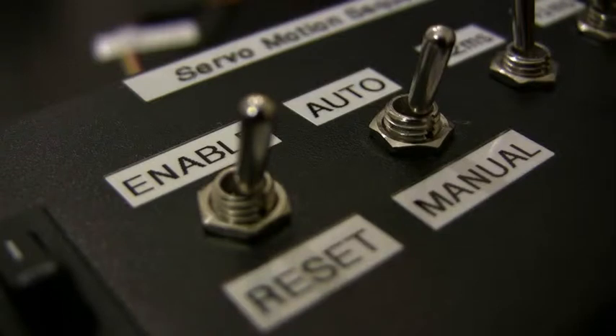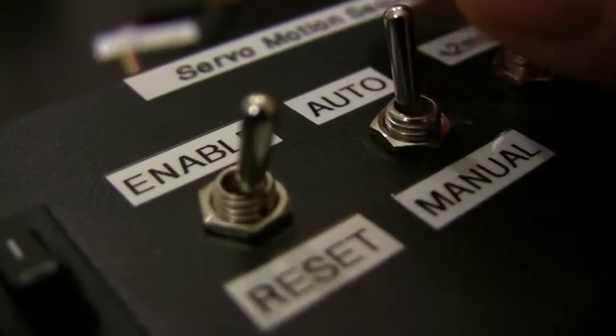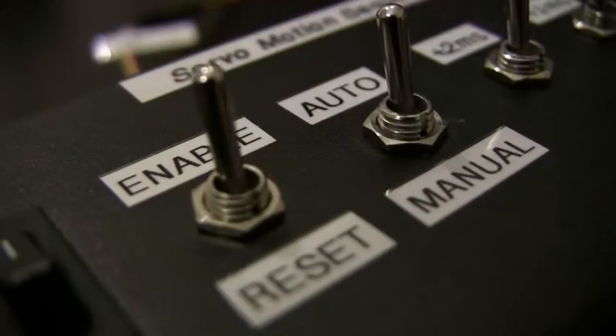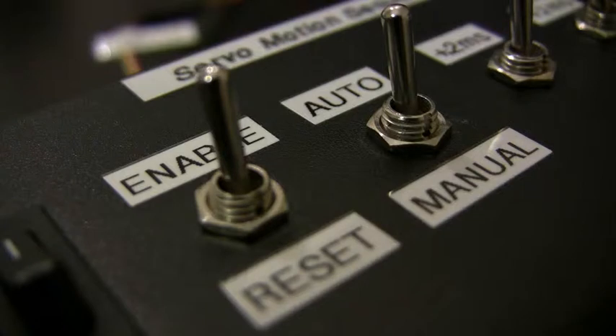For the final sequence, we'll leave the variable pulse switches both on so we have plus 0.3 milliseconds relative to the nominal, and the difference right now we'll switch from manual to automatic. Then we'll enable the servo motion, and what this does is it goes through that timing sequence so the servo moves automatically without having to step it through manually.